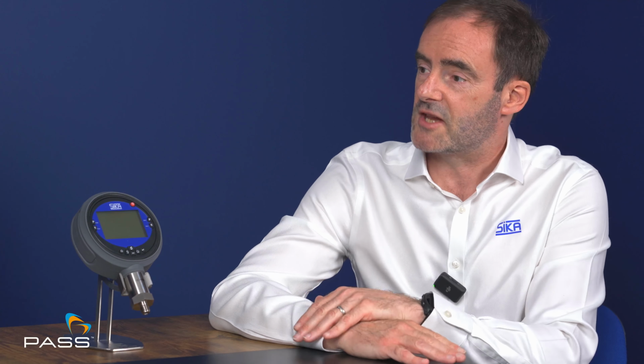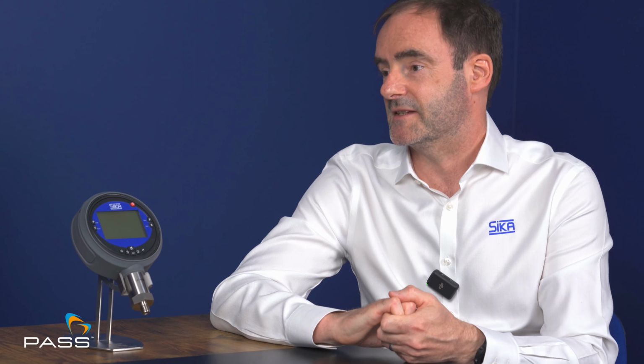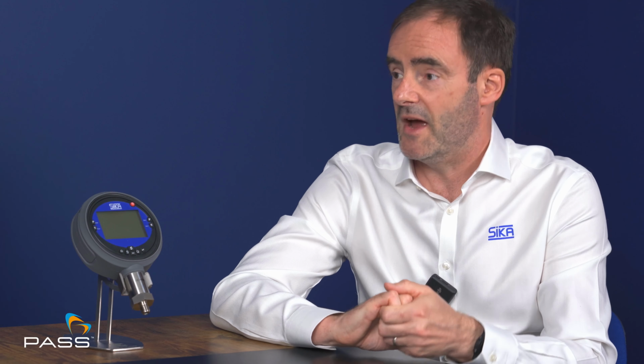So that's why we have the 3 different classes. And there's no point in having a very high accurate gauge when you've got a low accurate device that you're calibrating. So you would select maybe the lower class of accuracy, if you didn't need the high accuracy, to save some money, is that exactly right? Yes. There's cost levels between the different accuracy classes. So we see a lot of customers trying to calibrate pressure gauges, and they are typically 1.5%. There's no point in having a high accuracy calibration gauge for that. So we cater for different scenarios.